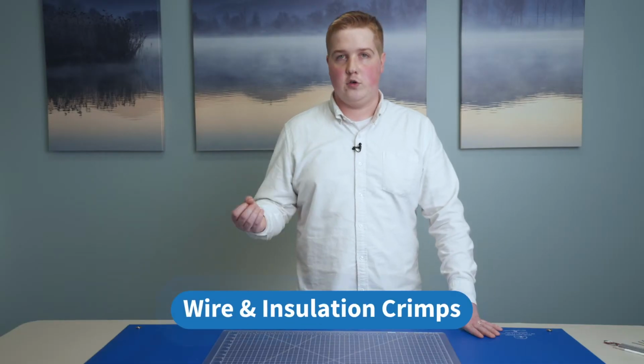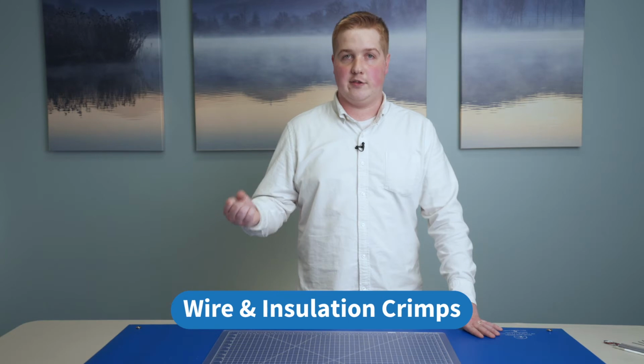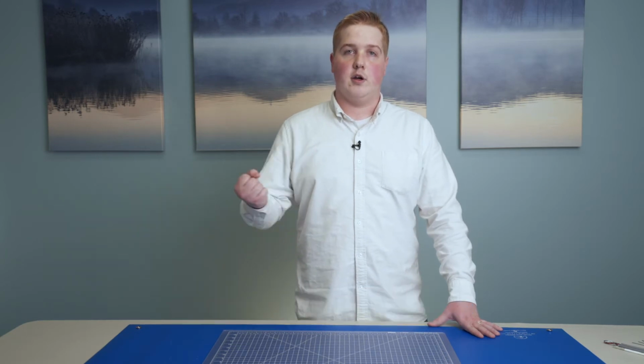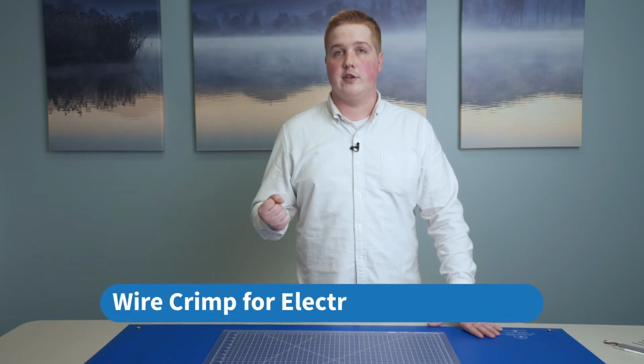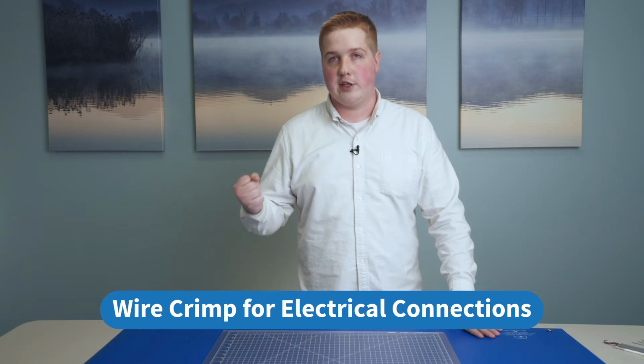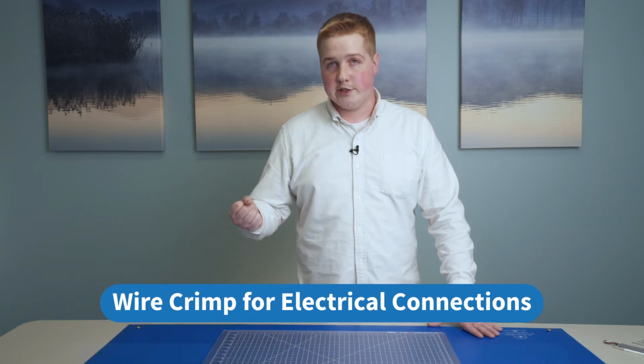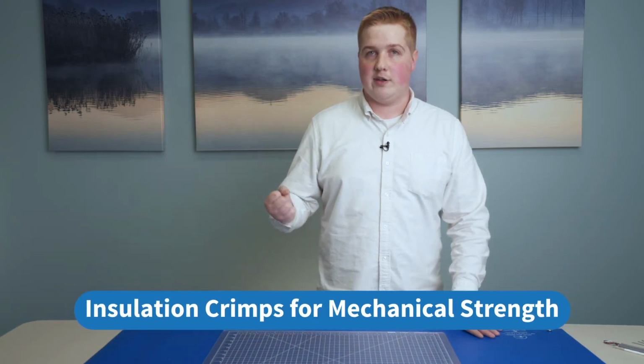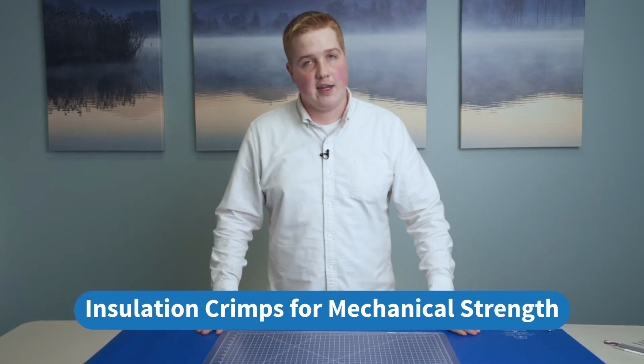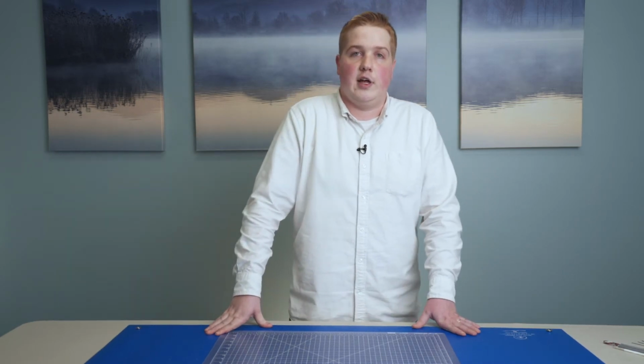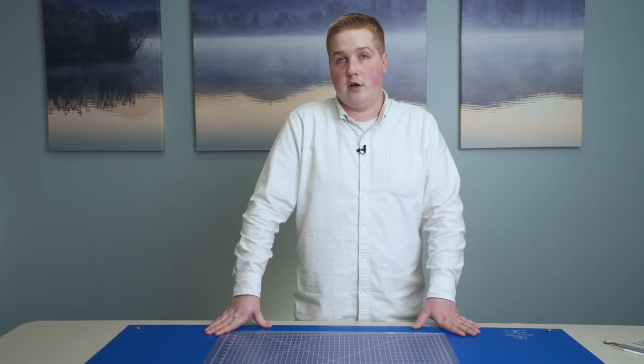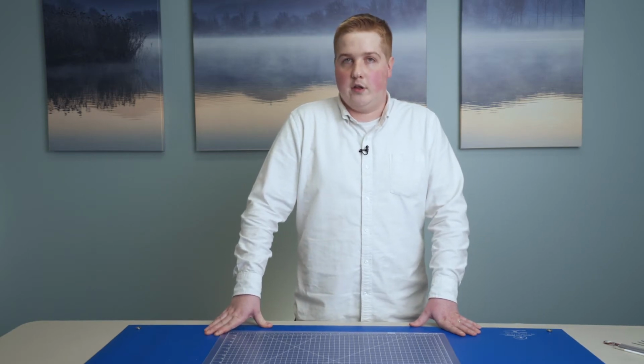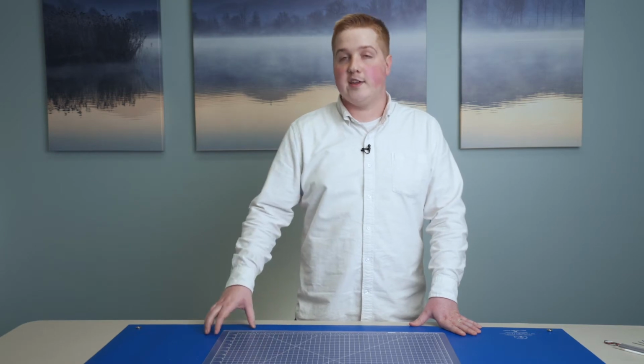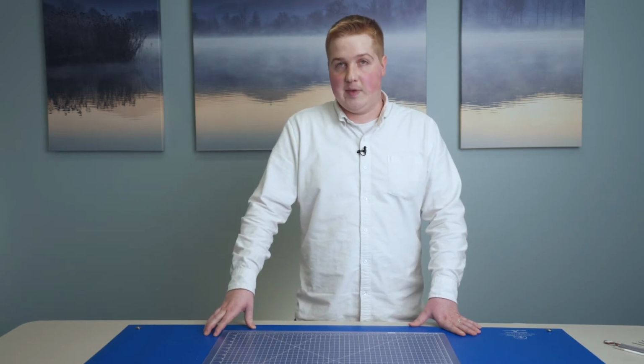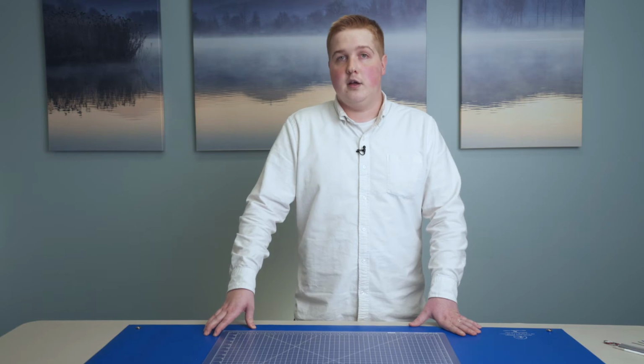A terminal has two different crimps on it. It has the wire and the insulation crimp. The wire crimp goes around the inner conductors and ensures a strong and electrically sound connection, while the insulation crimp attaches to the outer insulation of the wire and ensures a mechanically sound connection, so that additional strain is not put on the wire crimp and you are not breaking any strands. The issue can arise, though, where the terminal has a specified outer diameter limit that it can accommodate.